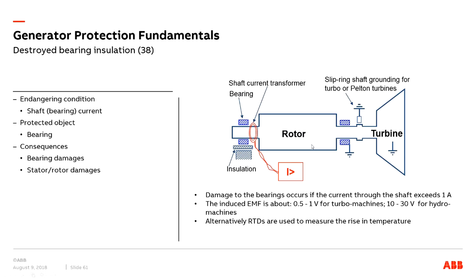And there is a bearing insulation protection. This is to protect the bearing insulation, in order to avoid excessive heating of the bearing. So if we don't take care of this, there could be bearing damage and stator and rotor damage. And so this is how we can do it. One of the ways is to measure the current here at the shaft. And alternatively, RTDs are used to measure the rise in temperature, and it can be integrated with the protection device to trip the generator.